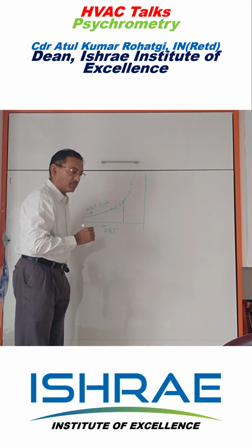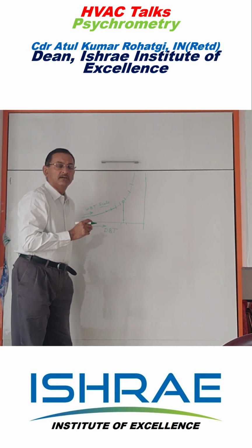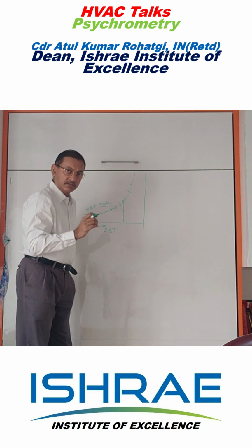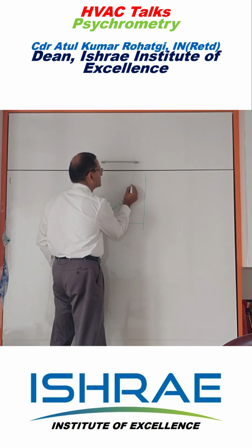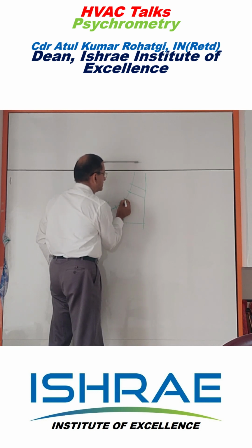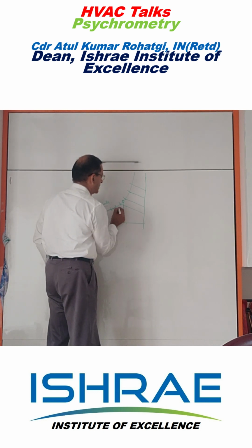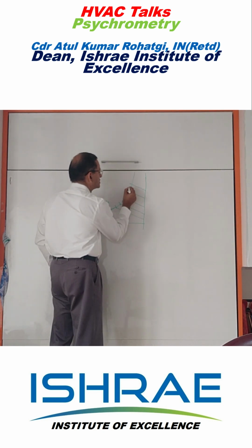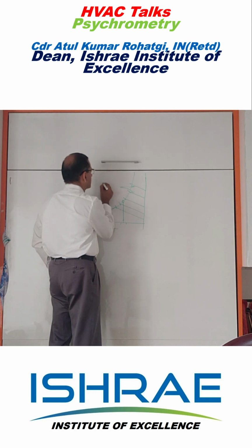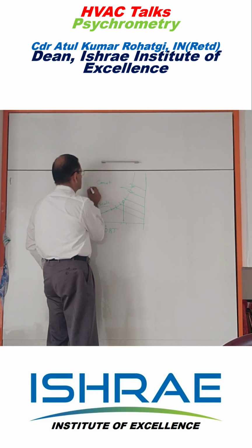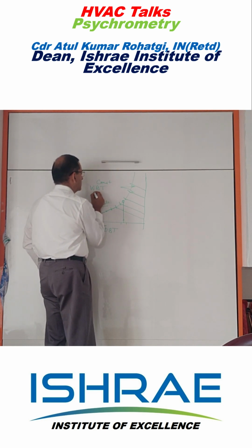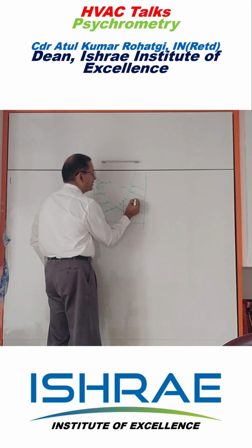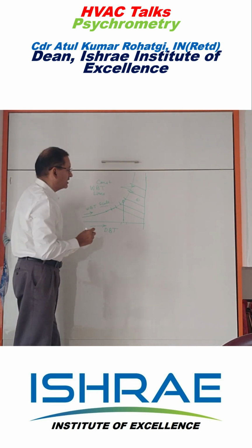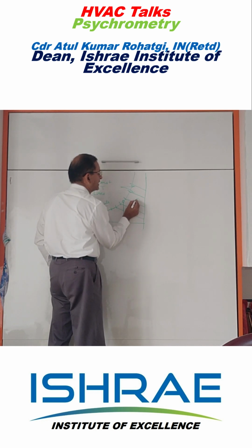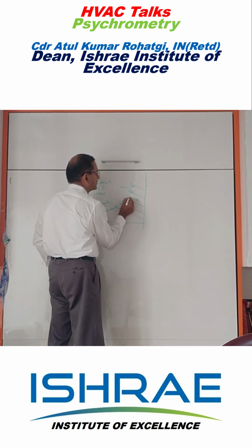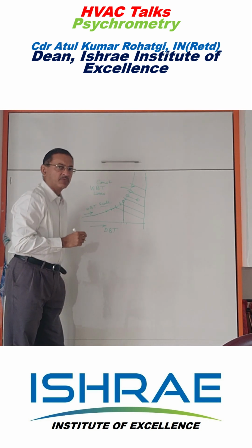The next thing we need to understand is where the constant wet bulb temperature lines are, and how we read them. On the psychrometric chart there are some dark lines, which are drawn like this. These lines are constant wet bulb temperature lines. So if I have a point here and I want to know the wet bulb temperature at this point, I need to draw a line parallel to these constant wet bulb temperature lines, and the point of intersection will tell me the wet bulb temperature at this point.